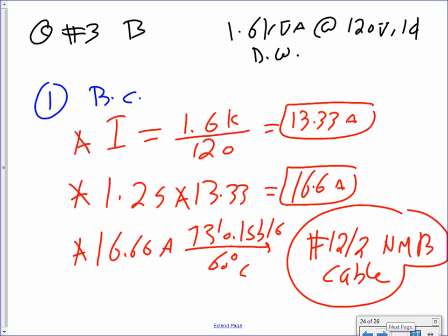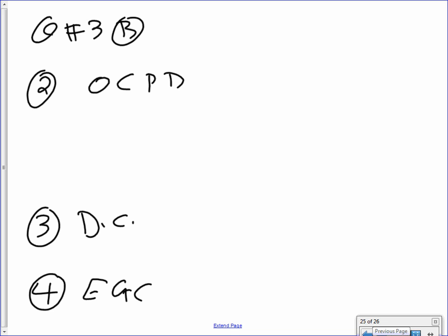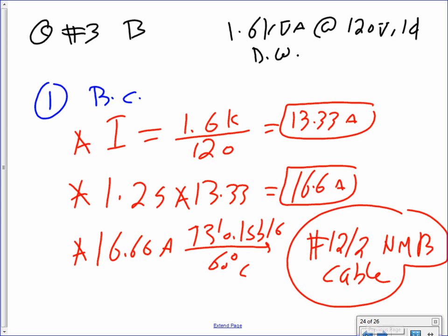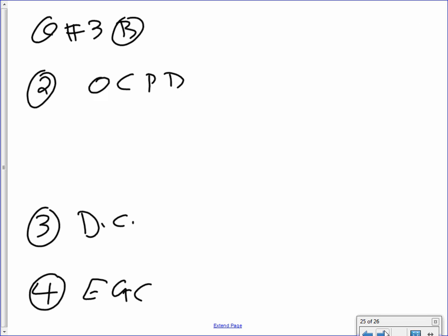Okay, the overcurrent protection device. Am I going too fast? Too slow? Go back. There you go. So, 12 NM cable. That's it. Now let's go to the overcurrent protection device. The same thing, guys. Very, very clear. So I want to take my 1.25, multiply it by, what's the full load current of that board? 13.33 amps. That'll get you a healthy 16.6 amps.